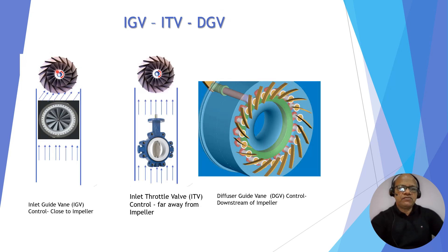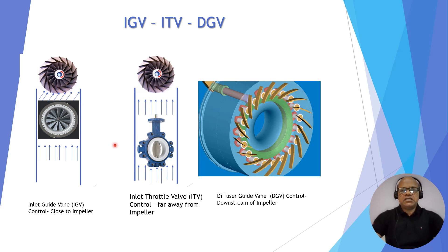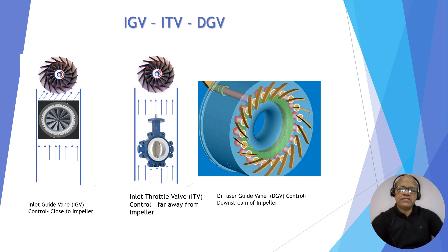You can see the first picture is for IGV, the second picture is for ITV, and the third is the diffuser guide vane (DGV). In the case of IGV, you can see the IGV is installed very close to the impeller, because the gas is turned in the same direction as the direction of rotation — that is called the pre-whirl condition. In the case of ITV, the flow is always axial, so it is not necessary to install it very close to the impeller; it can be installed further away. In the case of the diffuser, it is always installed on the downstream side, after the impeller.